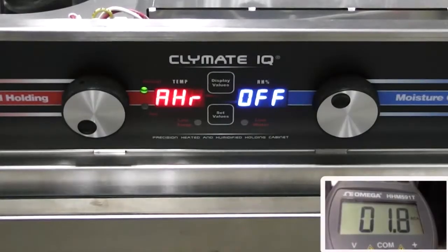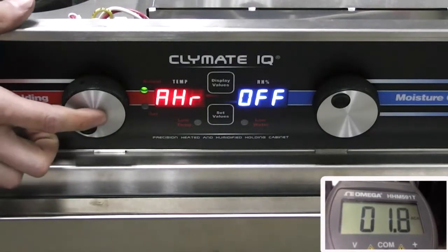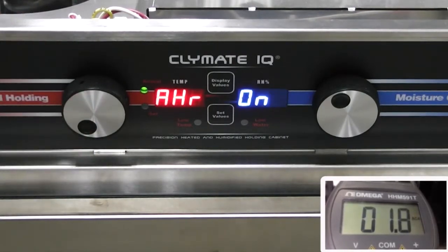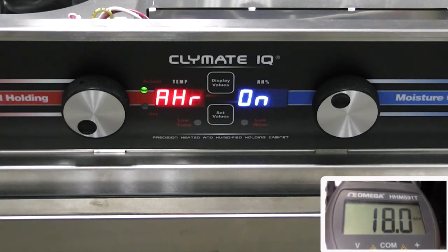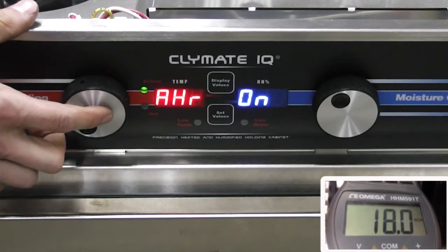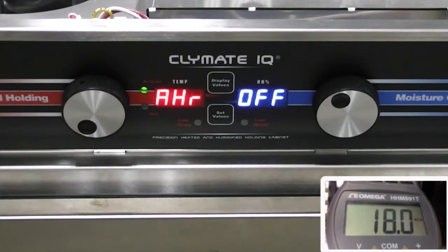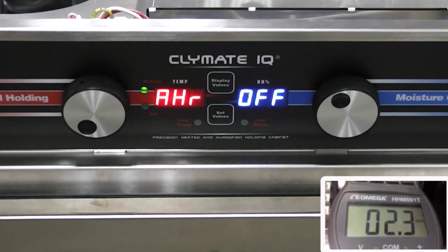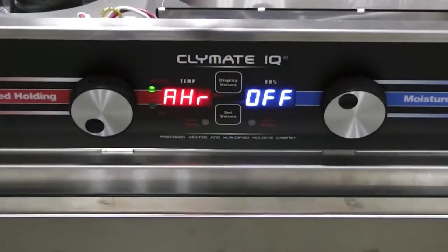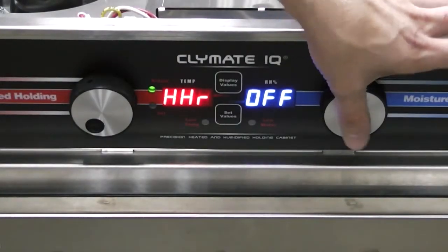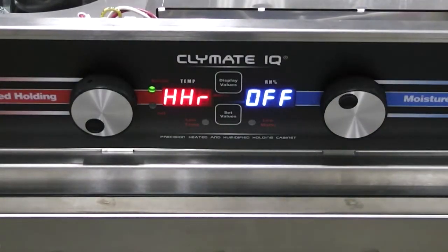Press the left encoder knob to turn the air heat relay on. The total amp seen should be approximately 25 for a PHTT 12P KFC or 16.7 for a PHTT 6P KFC. Turn it off and the motor amp should be approximately 2.1. Our total amps read 18, that's including the 2 amps for the fan and 1.9 for the motor amps. Press the right encoder knob to select the next parameter, the water heat relay.